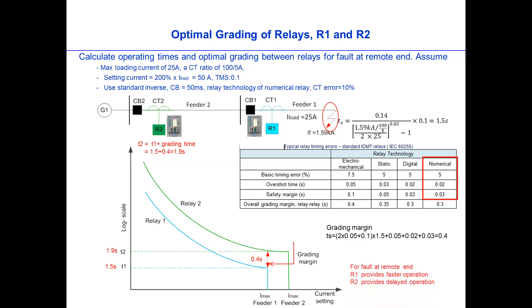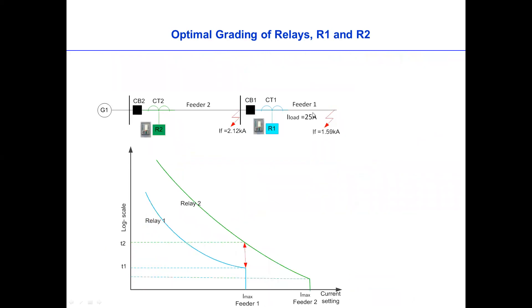What we can learn from this is, Relay 1 will provide faster operation, which is 1.5 seconds, and Relay 2 will provide a delayed operation. Of course, it has to wait for Relay 1 first to trip. The main protection is R1 for fault at the end, and R2 will provide backup for this fault.